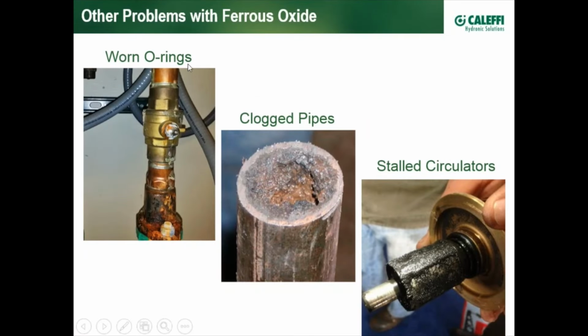Other problems: worn O-rings or even mechanical face seals on pumps, clogged pipes, and circulators, especially ECM type circulators, because they employ very powerful magnets in their rotors. And the same powerful magnets that deliver high efficiency in a pump also deliver the magnetism that attracts iron oxide, as you can see being built up here. Now, we were on this job site with these stalled circulators, and fortunately, our manager was able to clean them up and get them working again. You can see how abrasive they can be by the scoring on the end of this very hard shaft on this ECM circulator.